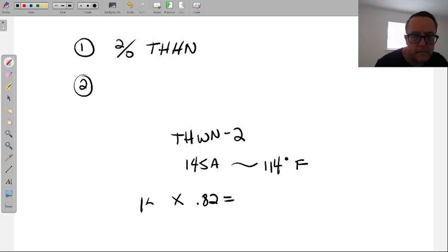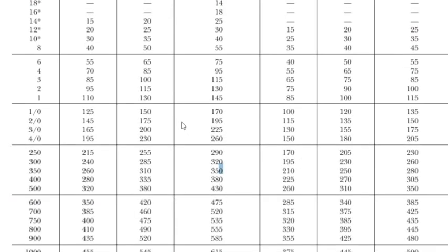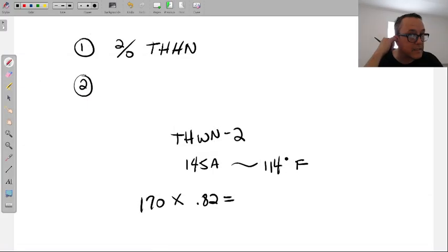You'd have to go up. Yeah, do you have to go up? Oh, I know why. Now I realize where we're at. 170, because 145, if I choose the 145, I know I'm applying a correction factor to it. If I choose this wire, the number 1, and I apply the correction factor, I know it's not going to be more than 145. I'm losing 18% of that wire. That's what the 0.82 is telling me. So I'm already starting at 1 wire size above it.